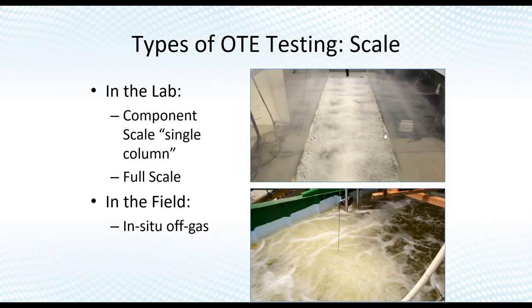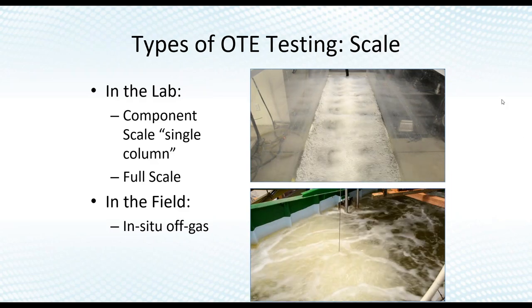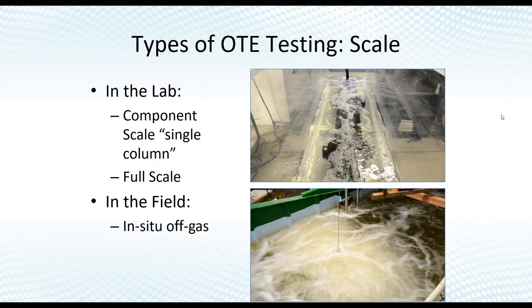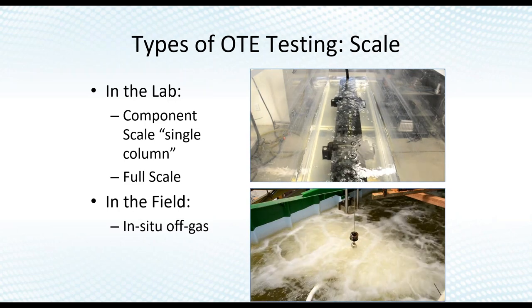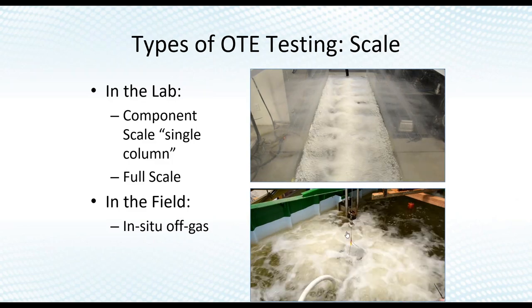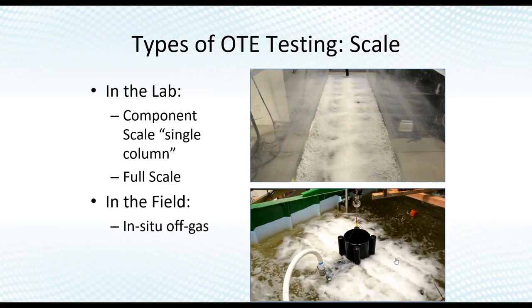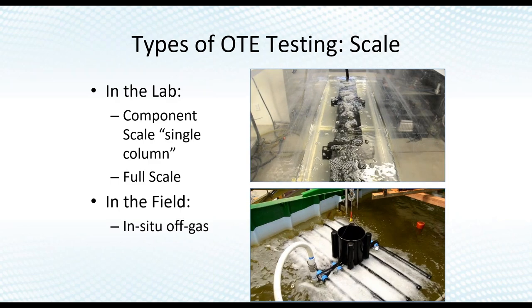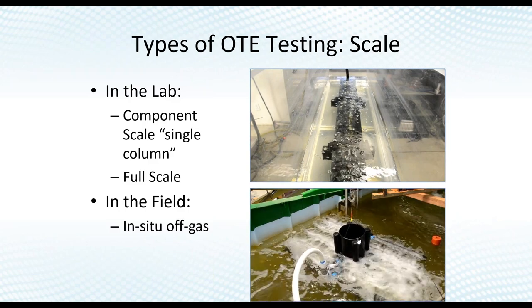There are also different scales of testing. Lab or component scale is where a manufacturer puts one diffuser or small component in a very isolated tank at maybe four or five feet deep under very ideal conditions. Full scale tests the entire device — not just one tube. The more full-scale you test, the more accurate you get, because you're evaluating the interplay of all diffusers together, including the currents from one side affecting diffusers on the other, and the influence of the coarse bubble diffuser.